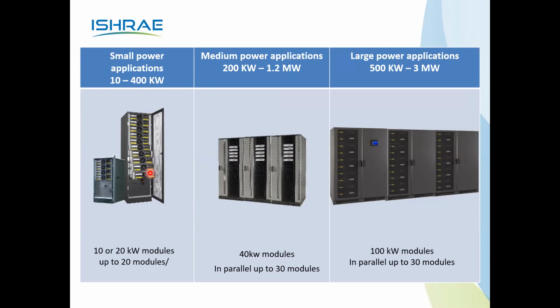Otherwise, the worrying part is the capex approval. That's the reason they go for the higher kVA rating from day one. But now with this topology, when the load increases, they can buy a UPS module, upgrade it and scale it, that too without any shutdown of the critical load.